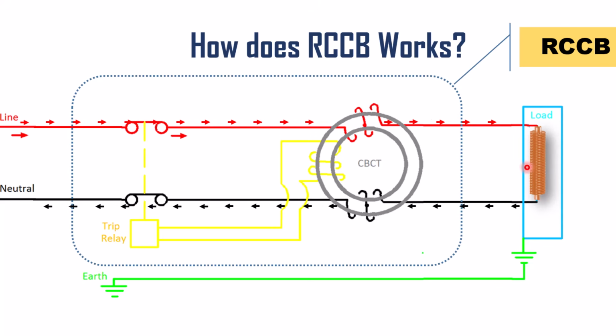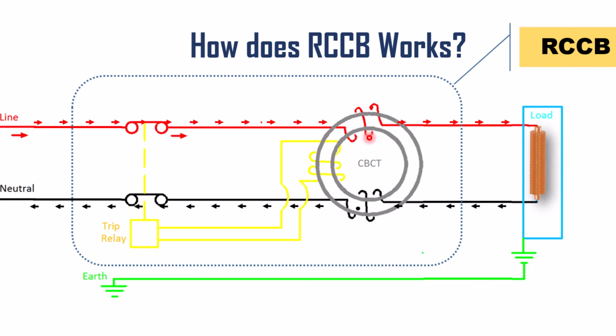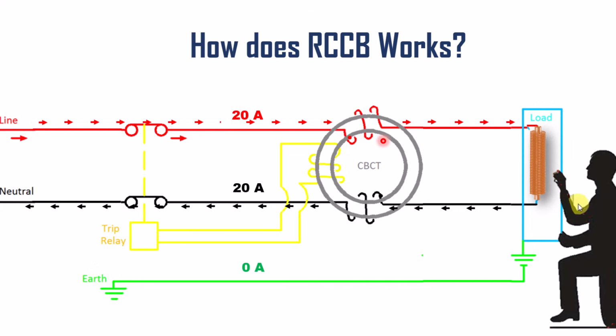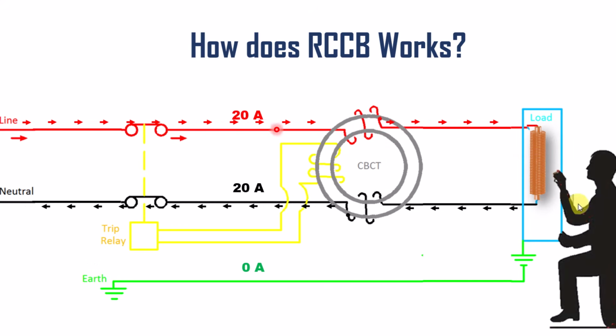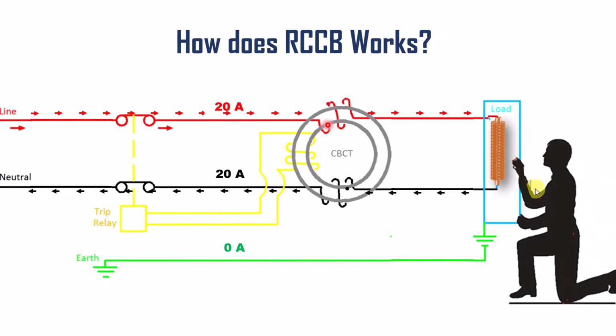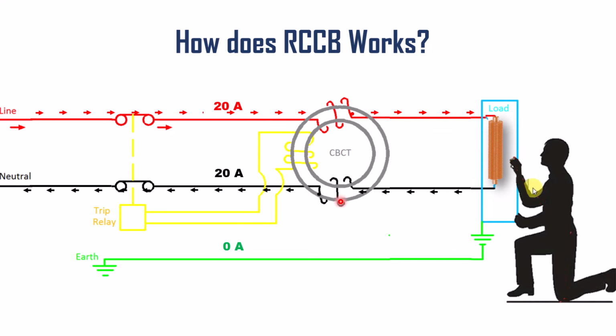Now let's try to energize this load. Here you can see the load is energized and the current starts to flow through RCCB. Now observe carefully that the load is drawing 20 ampere from the phase and the same current is flowing back into the neutral. So both the phase and the neutral currents are the same. Therefore, the net magnetic field of both the currents is zero and there will be no current induced in the secondary of this CT. But this happens only when no leakage current is detected by RCCB.